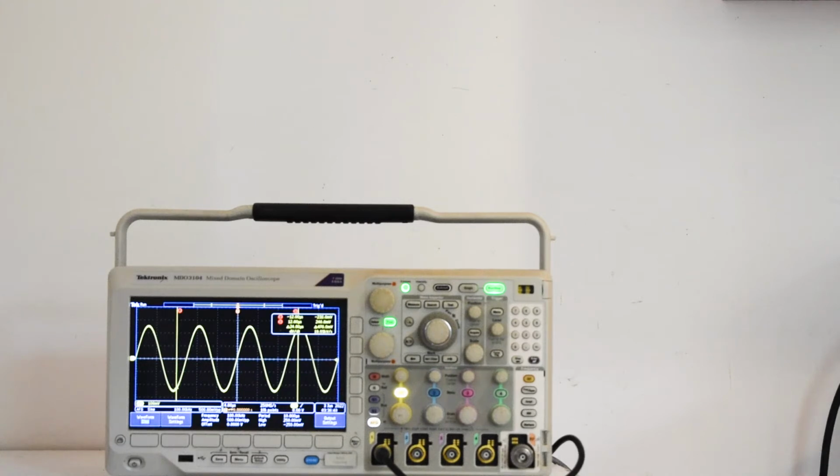Below the on-screen waveform at the right edge of the display, the trigger level icon shows the trigger level with reference to the waveform. The icon color corresponds to the trigger source color. In the second to bottom readout, the trigger readout shows the trigger source level. The trigger readouts for other trigger types show the parameters.